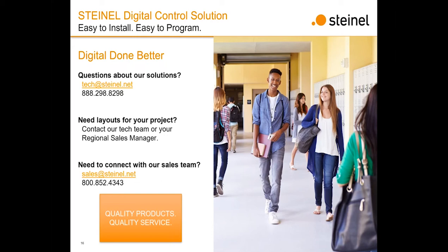Our first question: is this system designed more for room control versus an enterprise system? We try to get out of the pure room control philosophy, but it is geared more towards that at the moment. So 3 separate rooms, or 2 rooms with a single zone and another with 2 zones, is absolutely more doable and feasible with the DCS, as opposed to networking 30 DCSs together. Full-on enterprise systems that need a centralized server to control 30 floors are not the best route for the current status of the DCS.